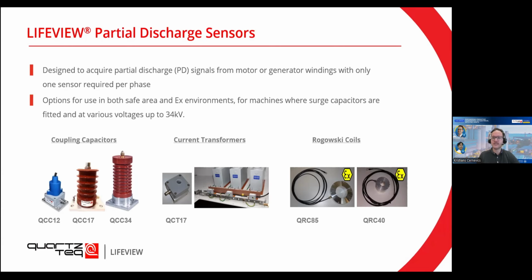Normally, for most machines, if it's possible, we would suggest installing the coupling capacitors, the ones on the left. Depending on the rating of your machine, so up to 12 kilovolts, 17, 34, we will install different types of coupling capacitors. These coupling capacitors filter the 50, 60 hertz signal, so only the high frequency signal, that is the PD discharges, will be let through. Inside there's also a voltage divider that will scale down the voltage, so we only output a very small voltage to the analyzer, so to the PDA2 or, for example, the mobile kit.